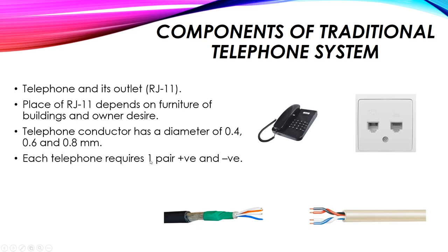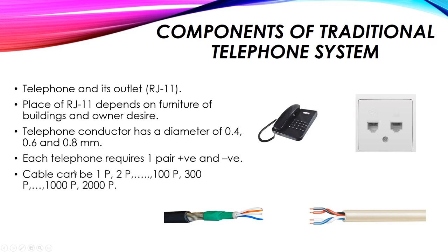Each telephone requires one pair — one positive and one negative conductor — so one pair equals two conductors. The cable carrying all telephone pairs can be one pair, two pair, 100 pairs, 300 pairs, 1000 pairs, 2000 pairs, and so on. The number of pairs represents the number of telephone lines, so for example if we have 100 telephones in a building, we need a 100-pair cable, with each pair providing one telephone line connection.